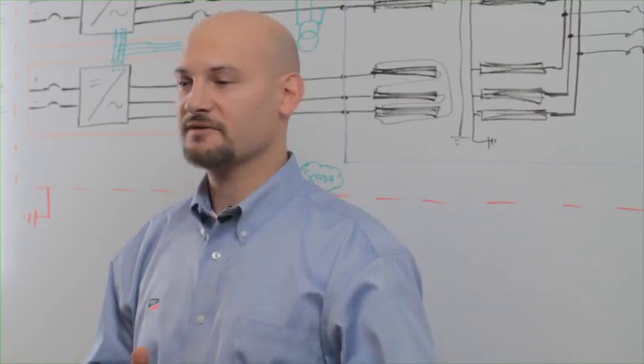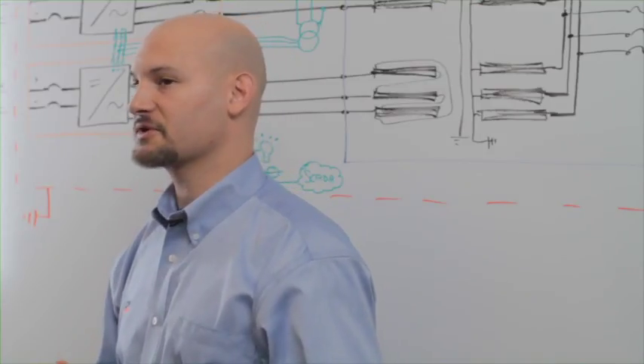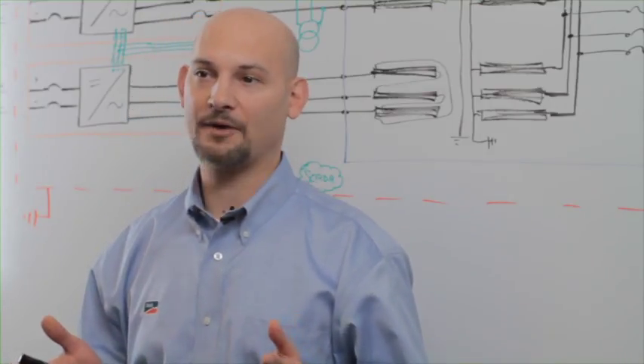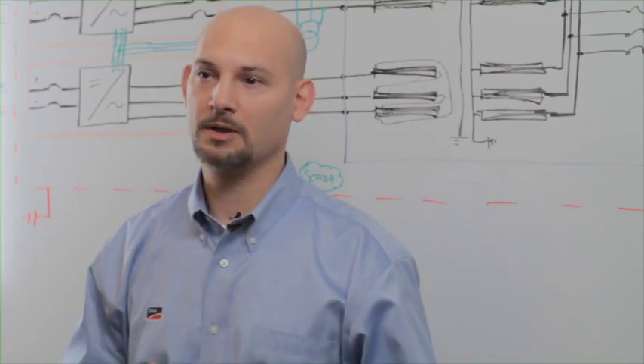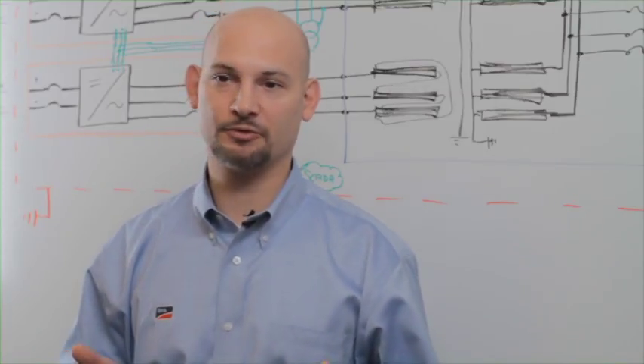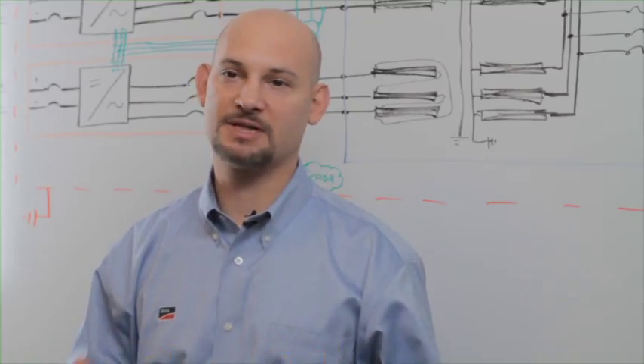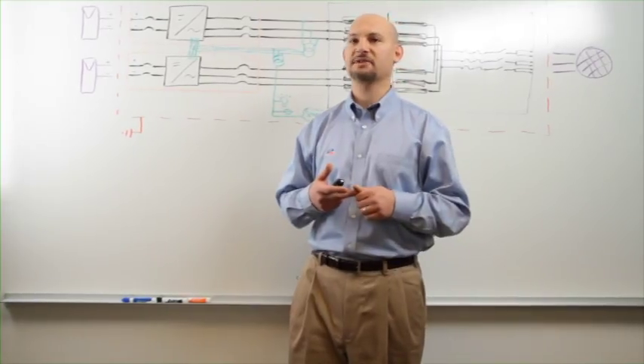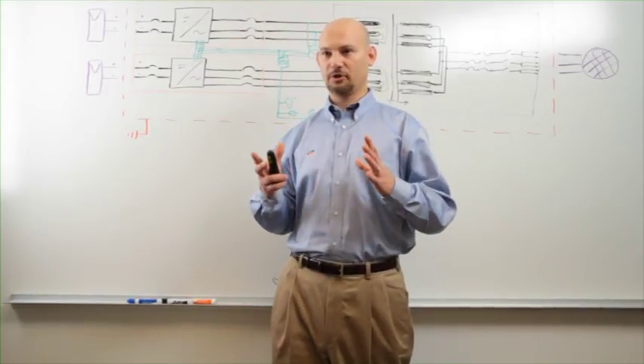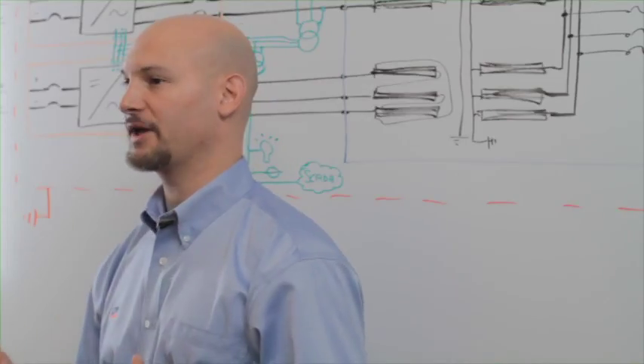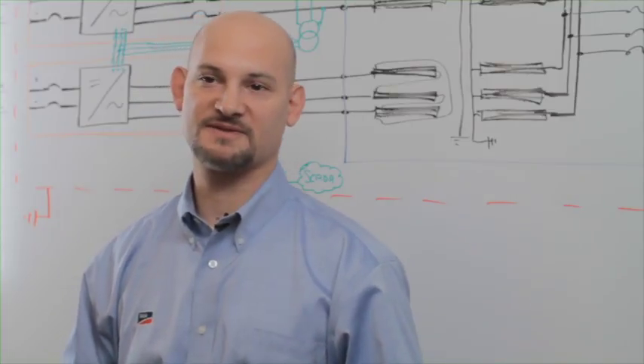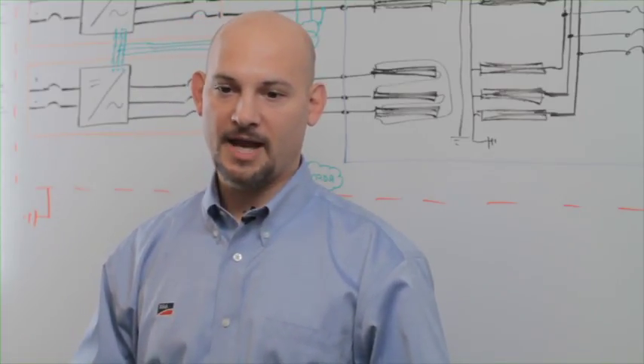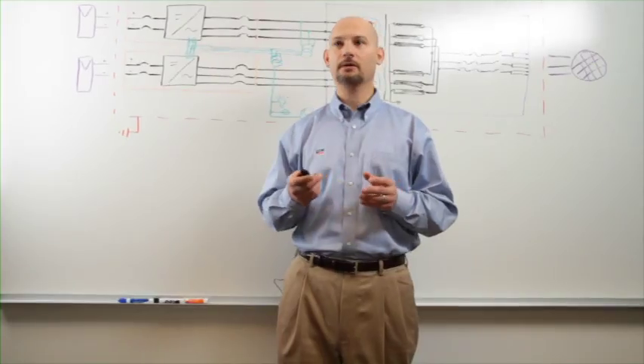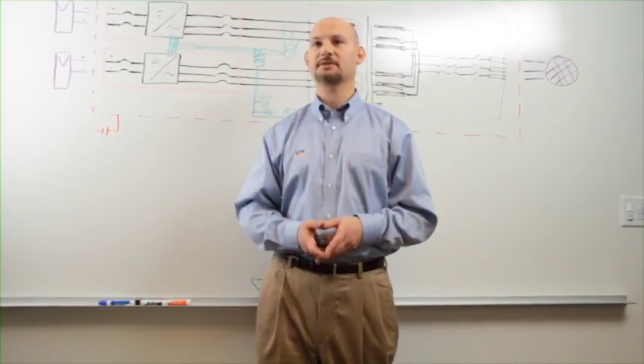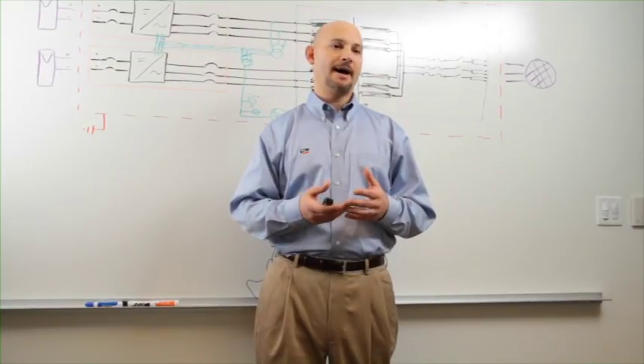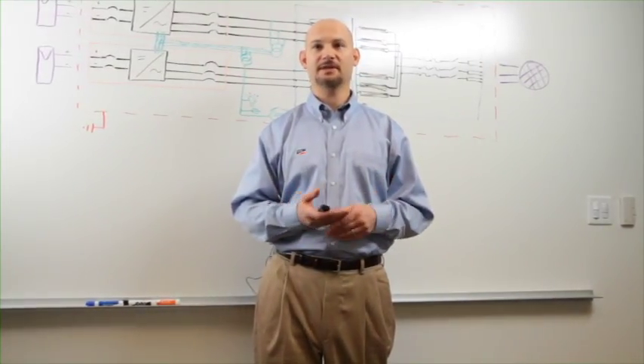The switch configuration of the medium voltage transformer is also configurable. You could have a simple on-off radial type switch, or more commonly found, it would be a loop collection system. So we are able to offer T-blade, V-blade, or say a 3-switch combination. And this is an oil-immersed load break switch that would take the place of, say, a standalone piece of SF6 switchgear.